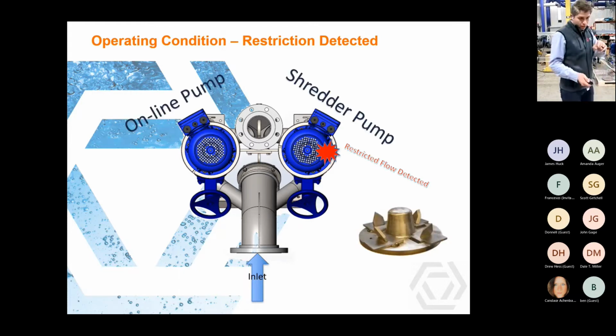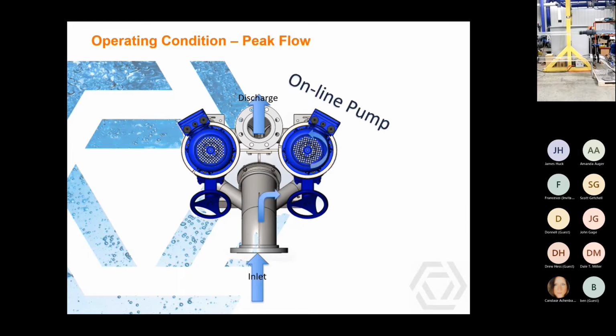Now watch the impeller on the right-hand side. Vanes fold down, exposing knives on the backside of those impellers. So as that pump turns around to remove whatever is in there, it's going to shred apart whatever is in that volute. And while that is going on, liquid is flowing through the secondary pump. The pump that was standby has now become the online pump, and the online pump is managing the flow.